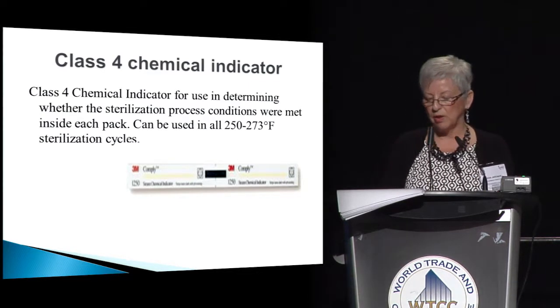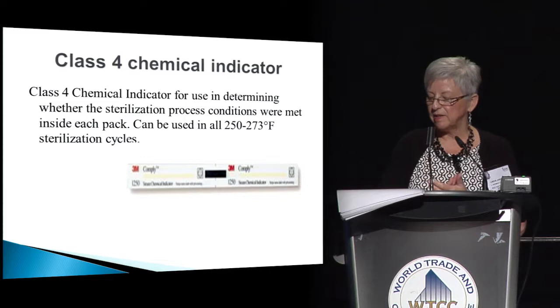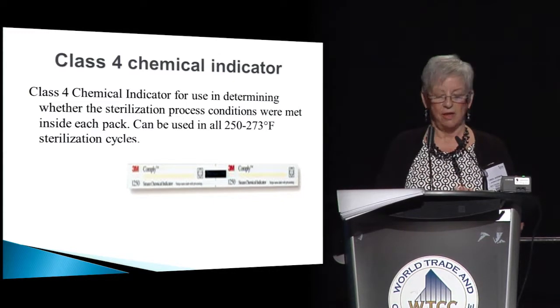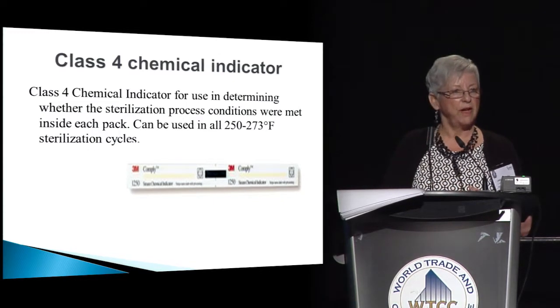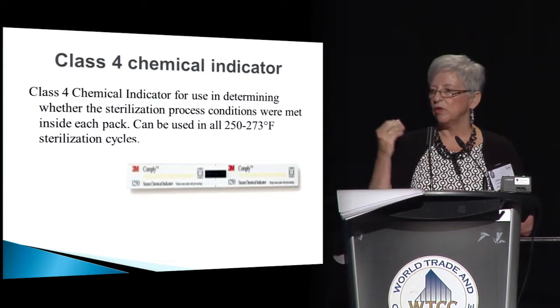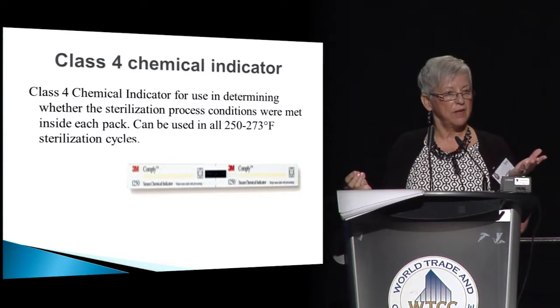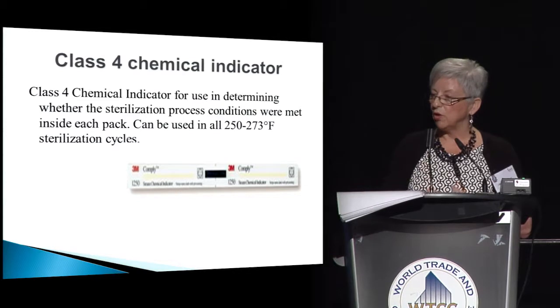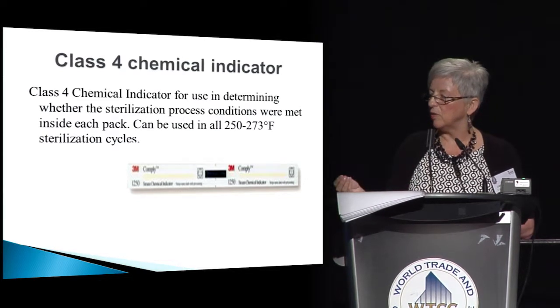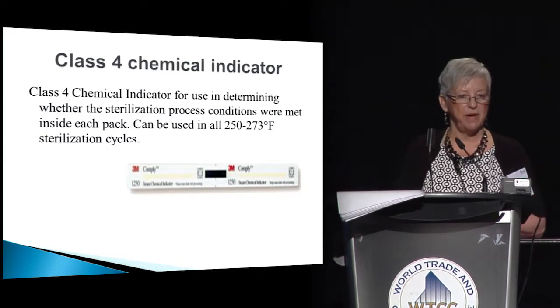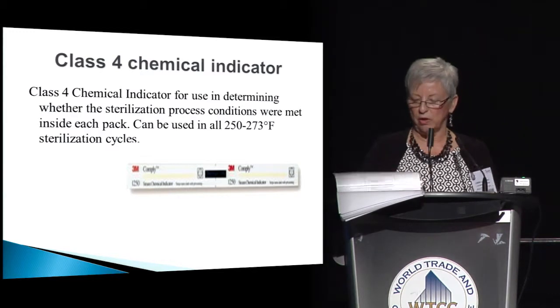A Class 4 chemical indicator is placed in each package prior to sterilization. And this indicator is read at point of use. You've looked on the outside and it's been through the sterilizer. When you look on the inside of the package, you're going to find this chemical indicator and say, the steam has made it here. So that's what you want to know.